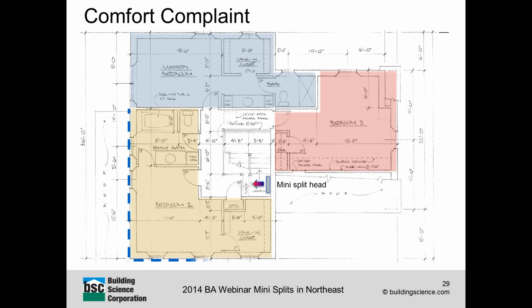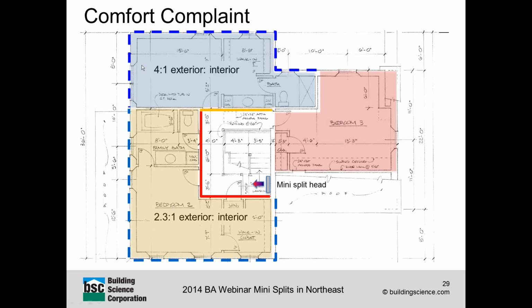Remember what I was saying before about the rate of heat flowing out of a room versus what's going into it through partition walls and doorways. You can see the ratio of the indoor walls to the outdoor walls for that front bedroom versus that back bedroom. If you ballpark out those ratios, it's like 2-to-1 versus 4-to-1. So it's not very surprising to me that that rear bedroom is slightly colder. You can also see that the rear bedroom has only a little bit more in terms of glazing that will get some of the morning sun and the south-facing sun.